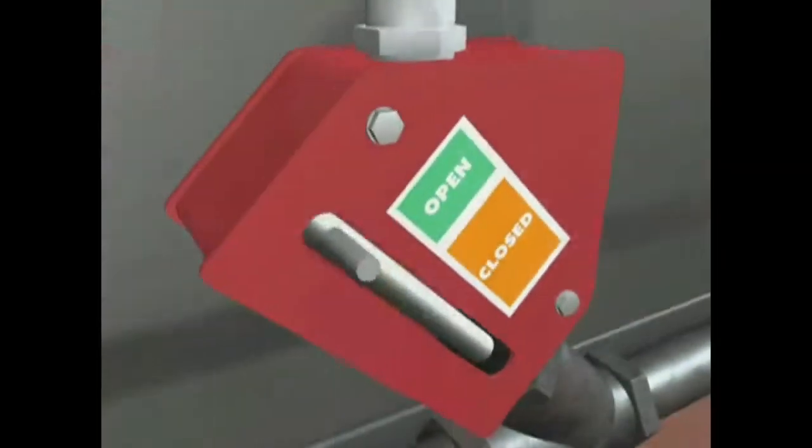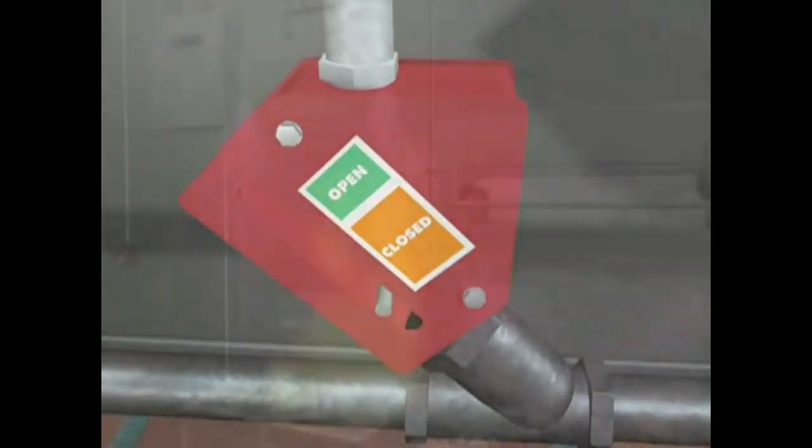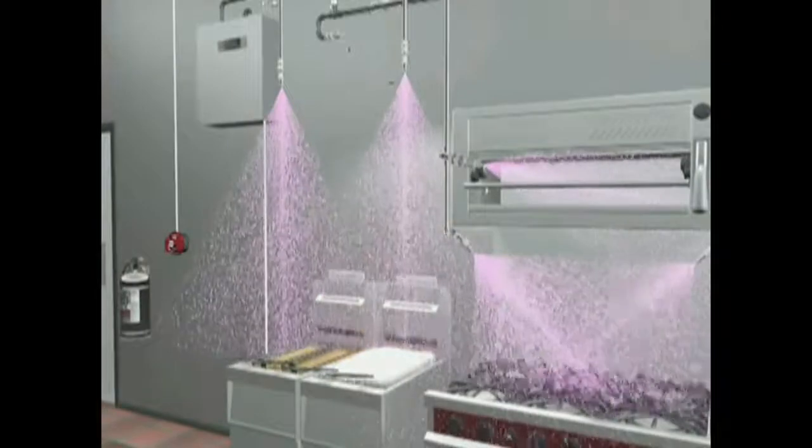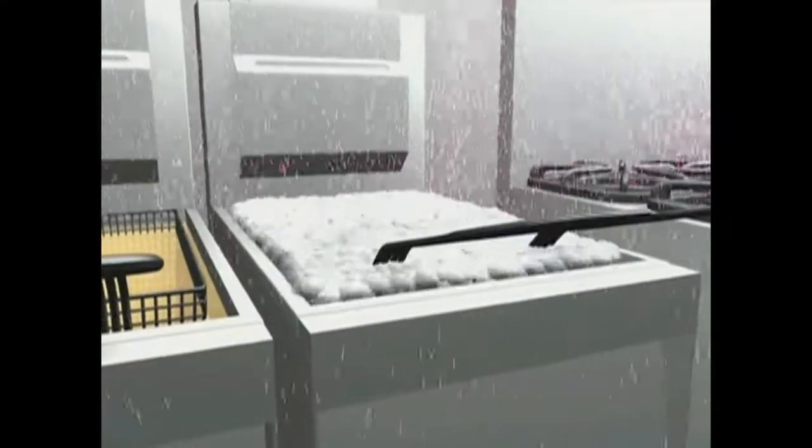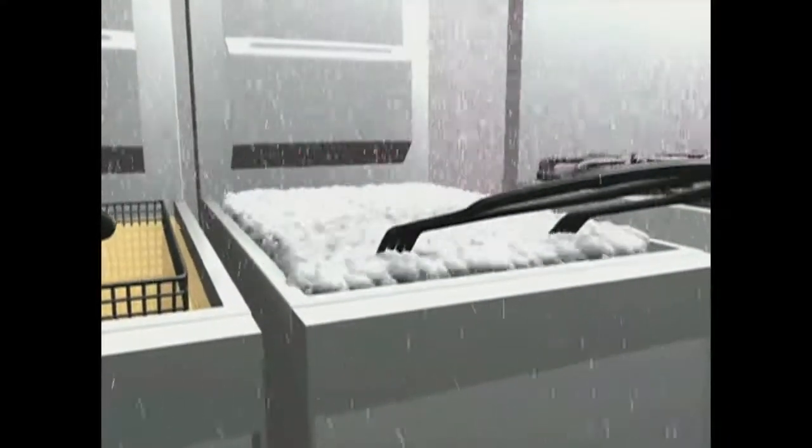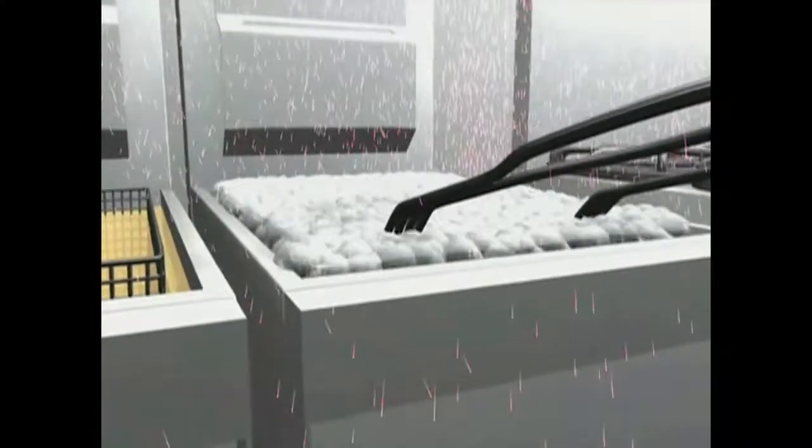an air cylinder is pressurized, tripping the Ansul mechanical gas shutoff valve. The discharged chemical reacts with the hot grease to form a vapor-securing blanket to help prevent fire reflashes.